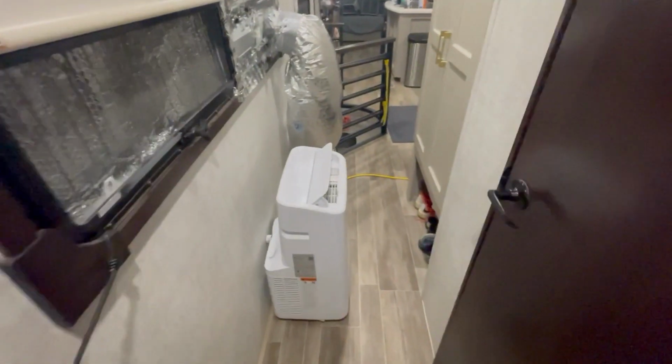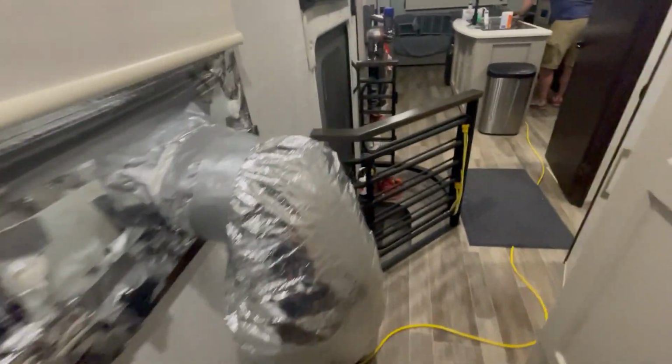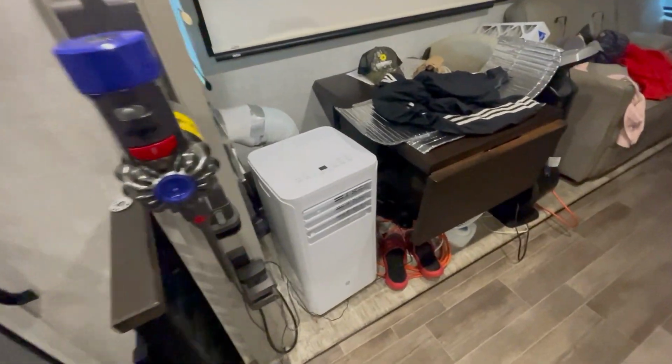Now you can see this gentleman, because of the problems he was having, he had these window units in here. He had one here, and he actually had one back here, and he's double checking me right now with his digital. Normally we always check on the furthest one, but we're just kind of checking each other with his digital. And how much you got? You showing about 56 right there?